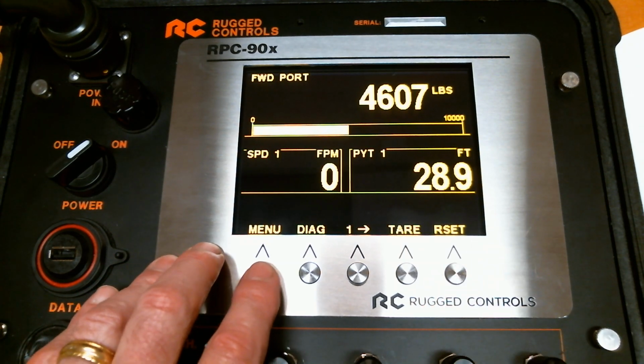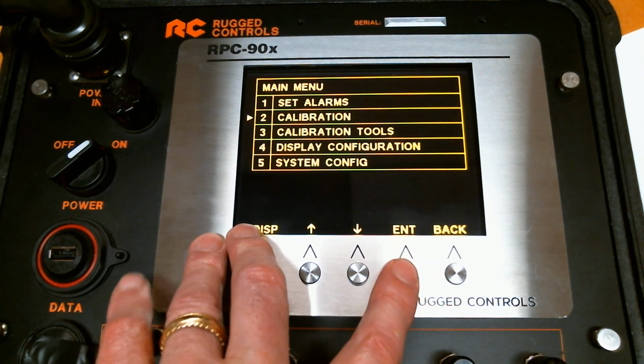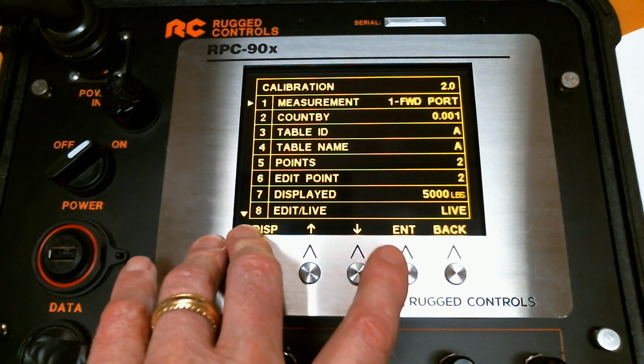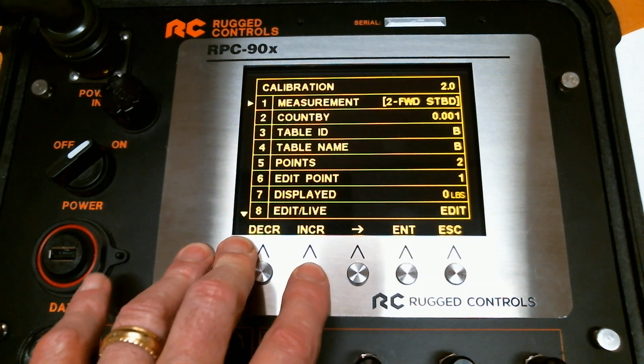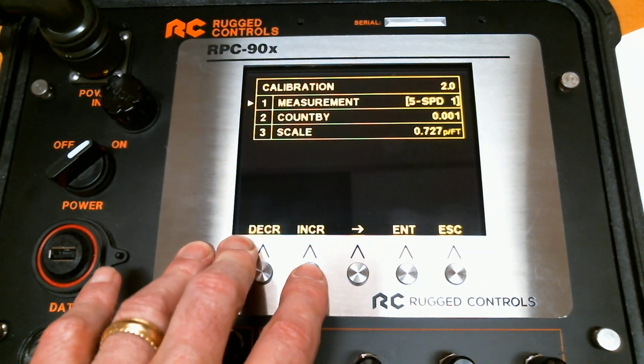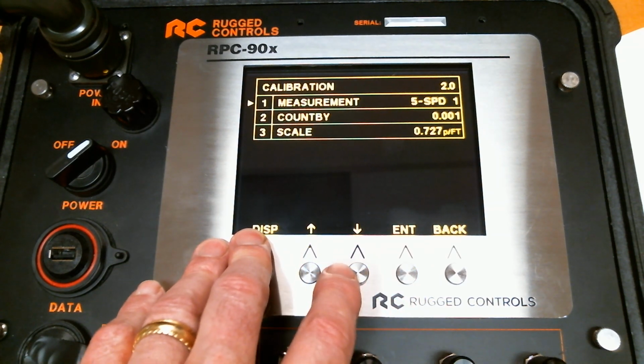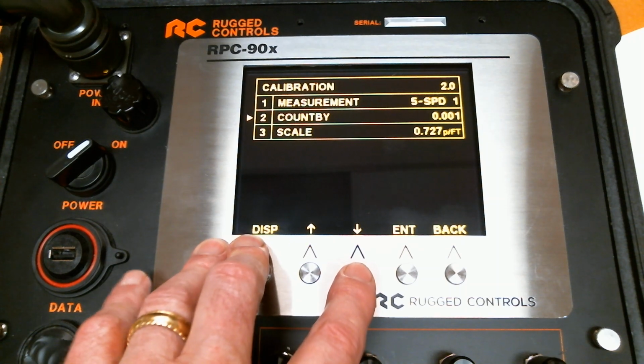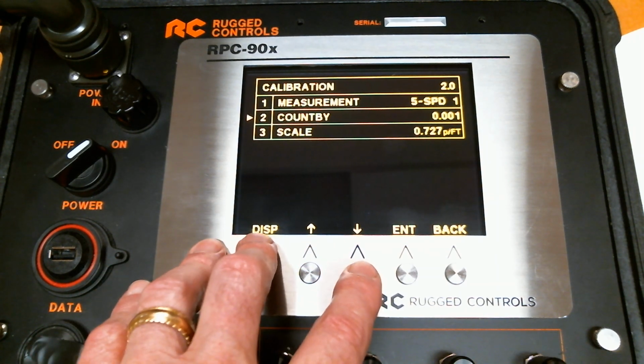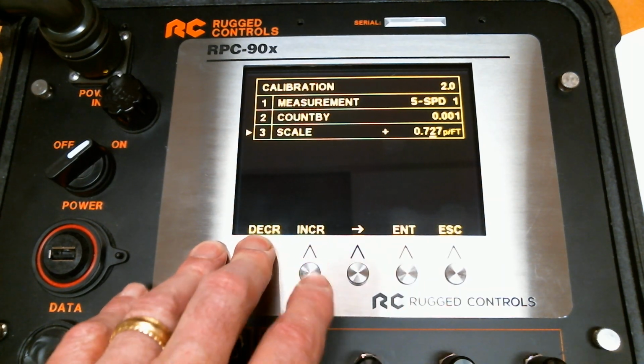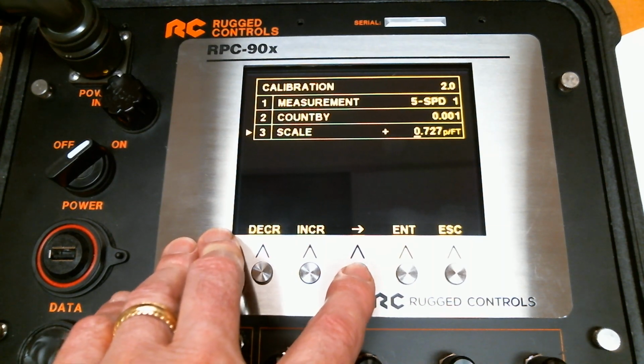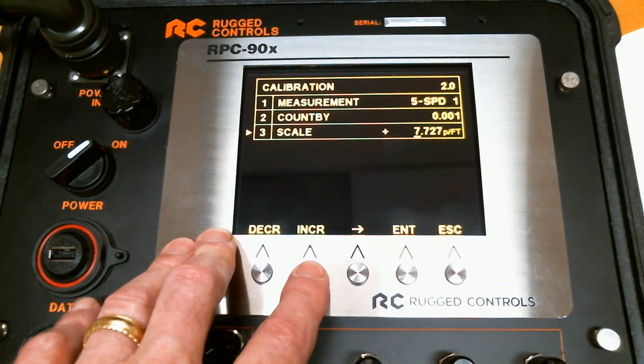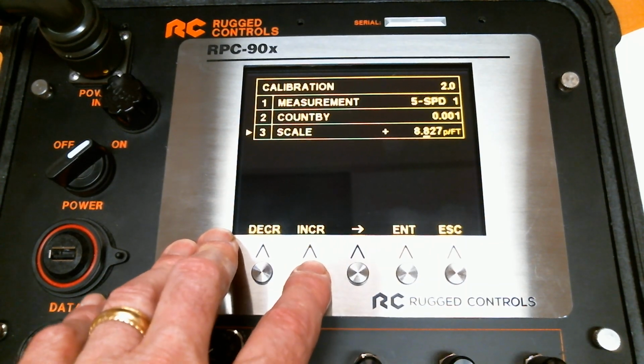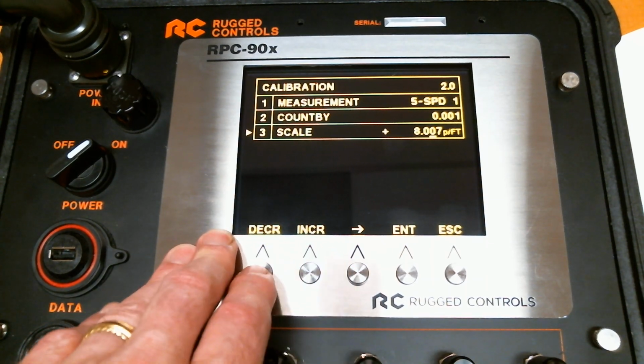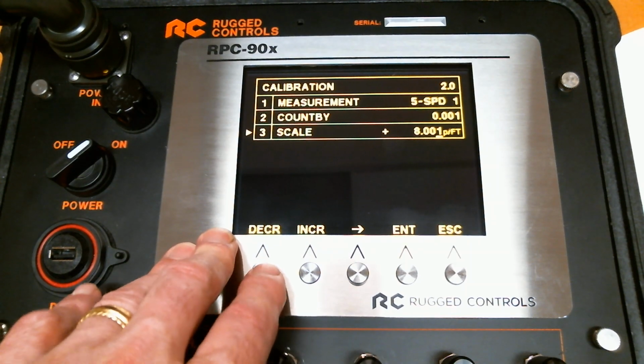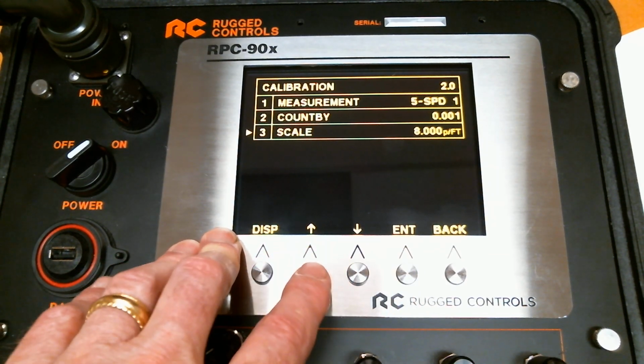So once we have that calculated, we'll move to the calibration menu, row 2, and we need to make sure we're on the right measurement. Let's do our speed number 1 first. Press enter to accept that. We're going to keep our count by at a very high precision, that is the runtime display resolution. And we're going to punch in our scalar that we just calculated. Let's say it's going to be 8 pulses per foot. And we'll remove the decimals. Okay, I press enter to accept that value. So that's the speed on sensor 1 that's calibrated.